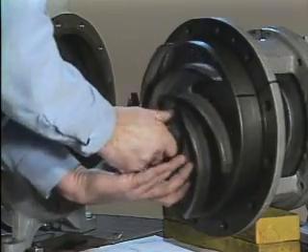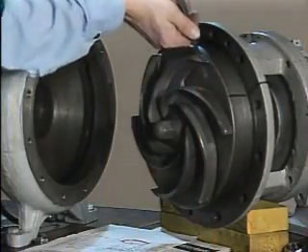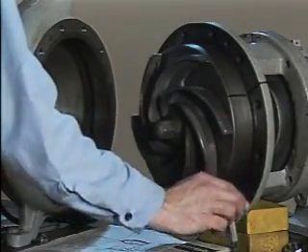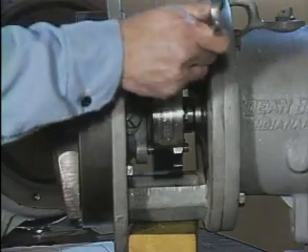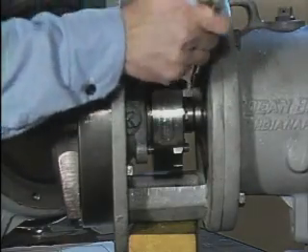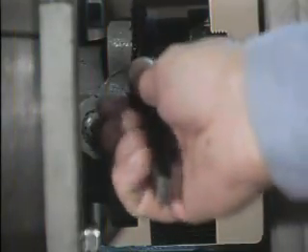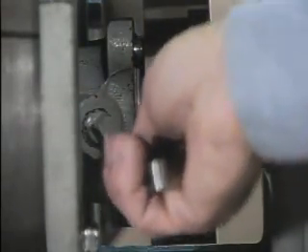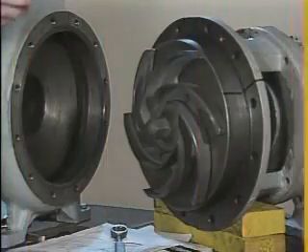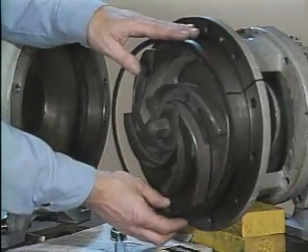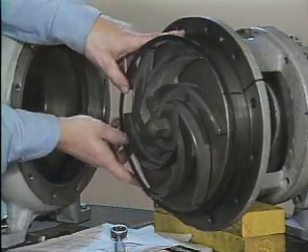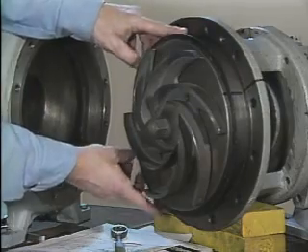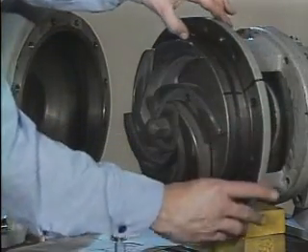Then the impeller is installed, and the clearance between the impeller and the back plate is checked to make sure that the components are properly positioned. Then the gland plate is bolted to the stuffing box. Next, the gap between the stuffing box and the gland plate is measured to ensure that the gland plate bolts have been tightened properly. Once that's accomplished, the seal installation is complete and the pump is ready to be reassembled and returned to service. To check your understanding of the procedures that we've covered, take a moment now to answer some questions.